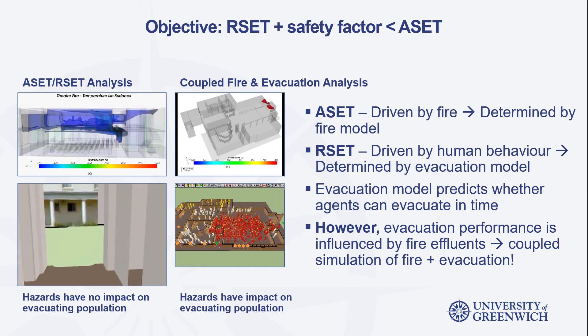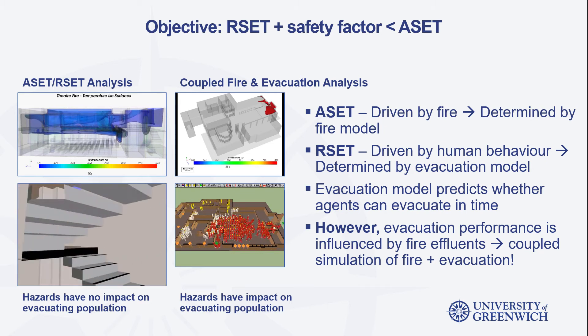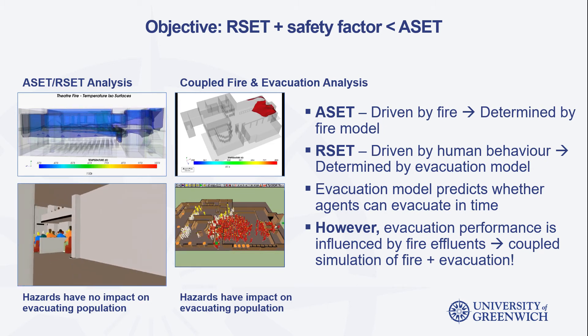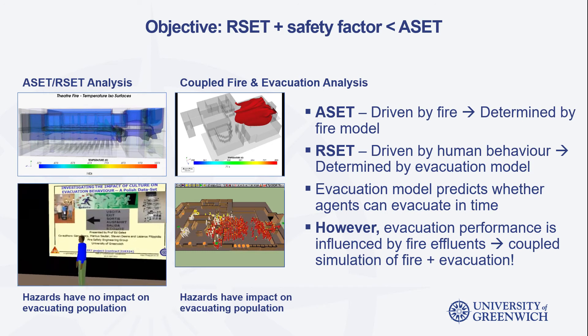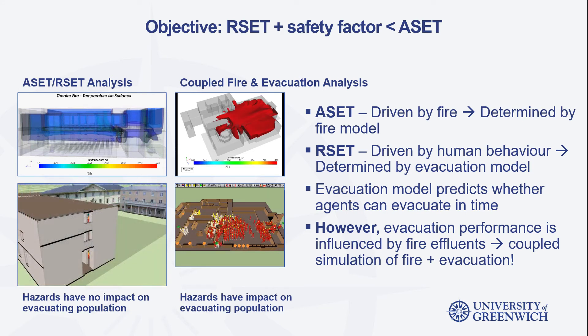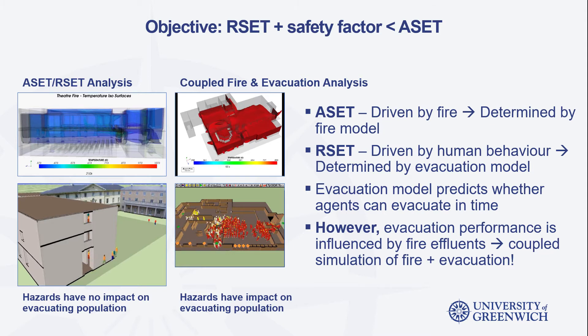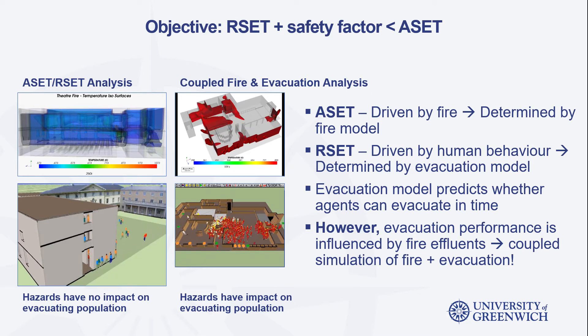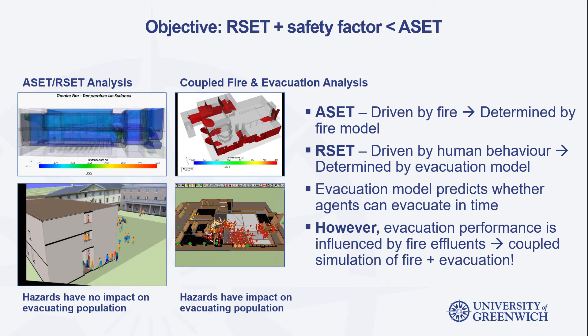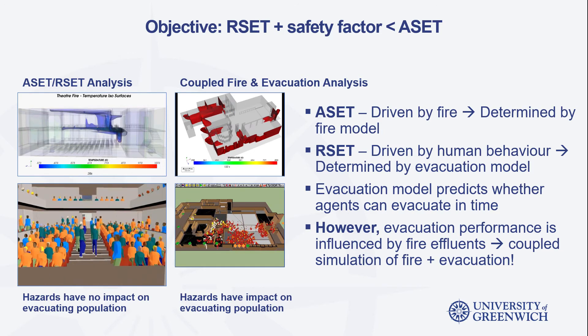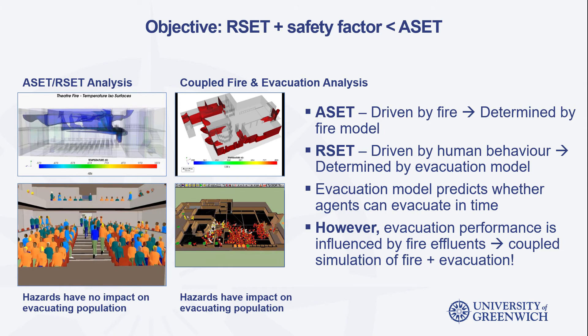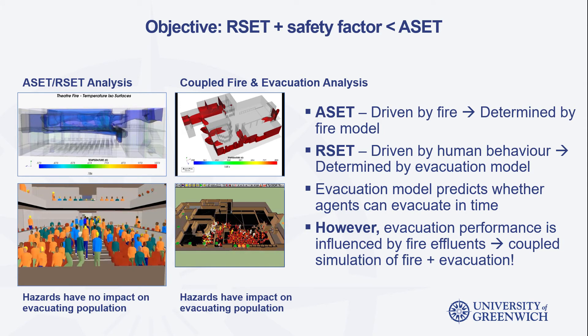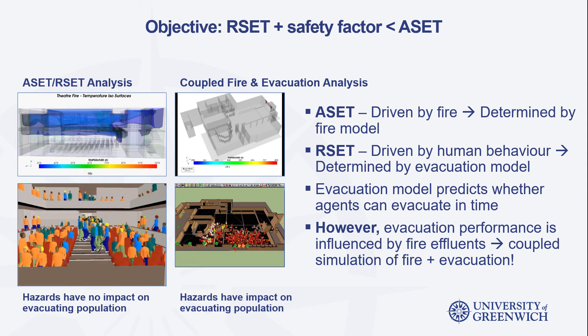ASET is a value that is driven by the fire development and the way that the fire effluents propagate, calculated using fire models. Conversely, RSET is driven by human behavior and is calculated using evacuation simulation models. The objective is to determine that ASET is greater than RSET plus a safety factor. The main reason why a safety factor is needed is to accommodate for the uncertainties inherent within the modeling tools, as no modeling tool can predict with absolute accuracy either the fire or evacuation process.